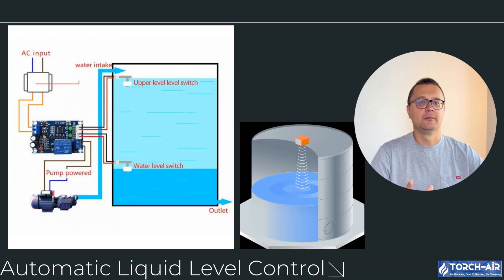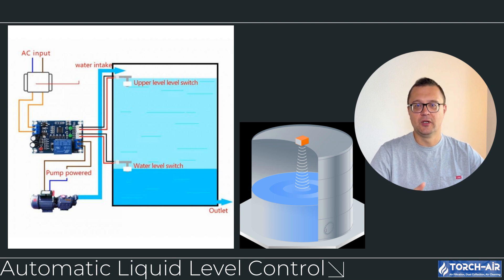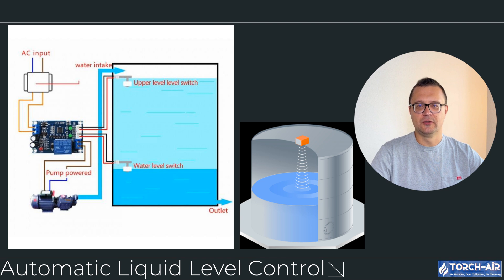Automatic liquid level control. Maintaining the correct liquid level in the scrubber is essential for smooth operation. Too little liquid reduces scrubbing efficiency, while too much can cause overflow and reduce overall performance. Automatic drain: when the liquid level reaches the maximum limit, the system automatically activates a pump to drain excess liquid, sending it to a designated drain or treatment system. Automatic refill: if the liquid level drops too low, the automated system triggers a refill, adding the required amount of water or absorption solution. Liquid level sensors constantly monitor levels in real time and signal when to activate the drain or refill function.